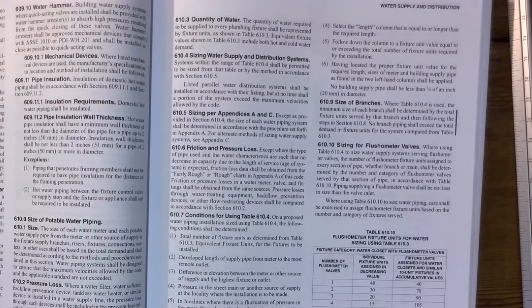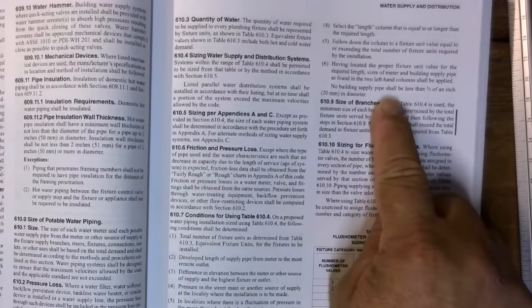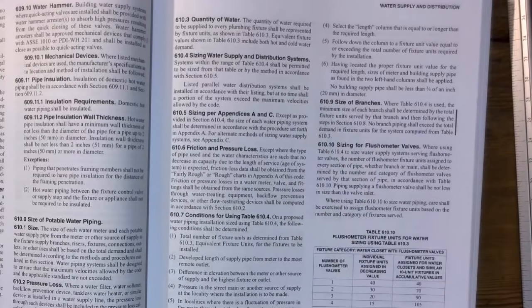Little key note here, right here. No building supply pipe shall be less than 3/4 inch. Now that's the supply going into the building. That's not like one of the branches when you're inside the building. That's actually going to the building from the meter. Cannot be less than 3/4 inch.